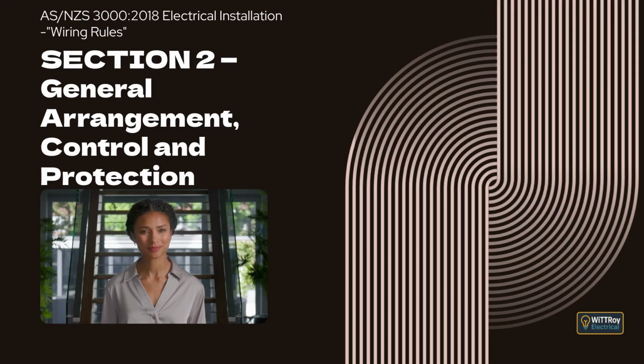Clause 2.6.3.3, Installation requirements, New Zealand only. This clause explains when New Zealand installations must have an RCD for extra protection. For residential installations, extra protection by an RCD with a maximum residual current of 30 mA must be provided for final subcircuits that supply one or more socket outlets, or one or more lighting points, or directly connected handheld equipment such as hairdryers or tools.